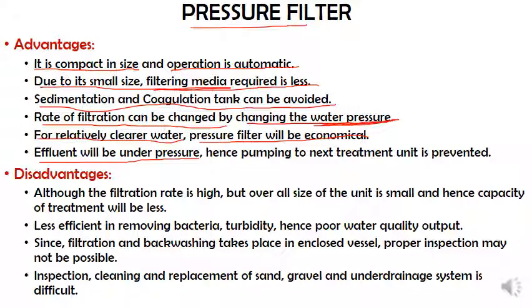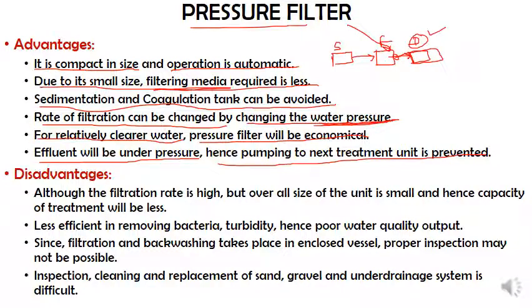Effluent will be under pressure, hence pumping to the next treatment unit is prevented. That is, usually this pressure filter is again one unit of treatment. Initially we studied the sedimentation process, then filtration, then let us say disinfection. From each unit, once the effluent comes out, we need to pump the water to the next unit. If you are using a pressure filter for the filtration process, the effluent will already be under pressure, so it will automatically rise to a higher level, and can be used for further treatment methods, whether it is disinfection or softening or any other technique. So pumping can be prevented if we use pressure filters.